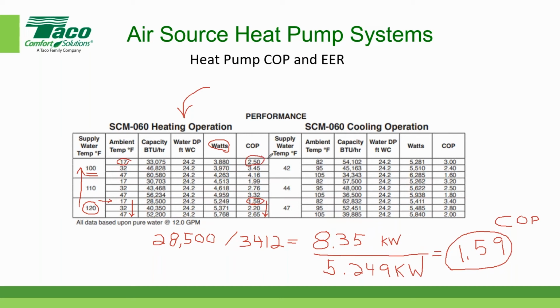So what impacts the COP? Let's make the obvious statement here. It's the discharge water temperature and the ambient temperature. The higher the ambient temperature and the lower the discharge water temperature, the higher the COP. This is important because when we talk about heating systems that run 12 months out of the year, the low temperature ambient conditions only take place about 5% of the total heating hours in a year.